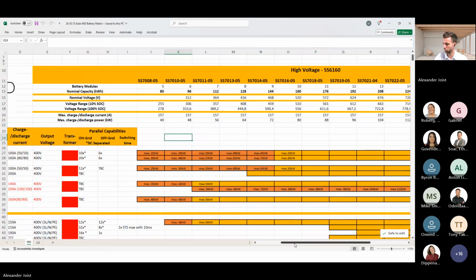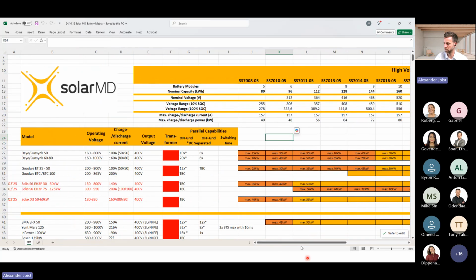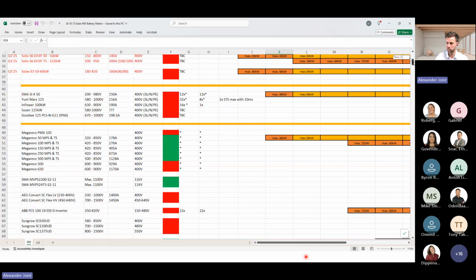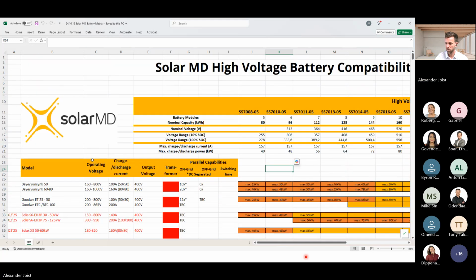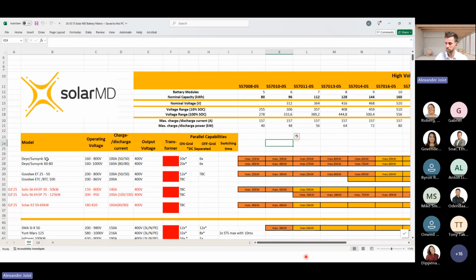So what we can see here in a compatibility matrix for the high voltage side is 13 inverters, all the different brands which are compatible at the moment with our battery. If we look at the GoodWe ET, the operating voltage is 200 to 800 volt, and the charge and discharge current is 100 amps. It's 2 outputs, which are 50 amps each, which can be paralleled to 1 output. So you have 100 amp of charge and discharge power.